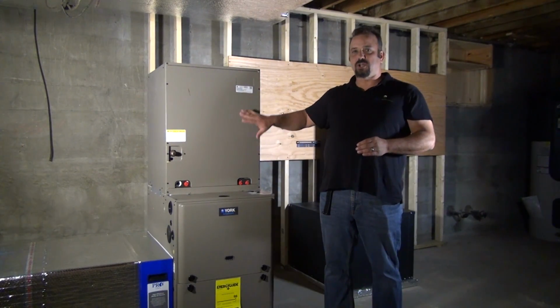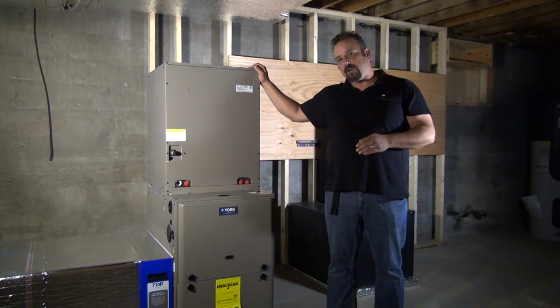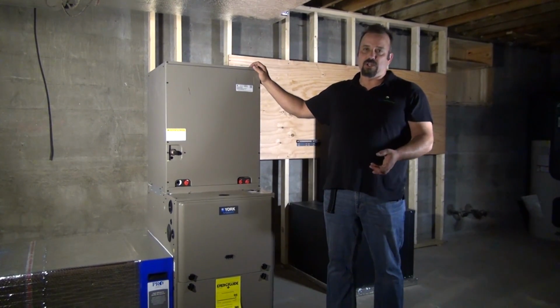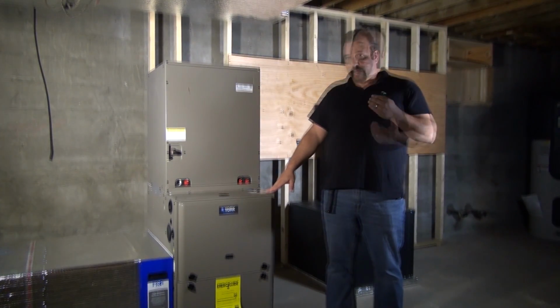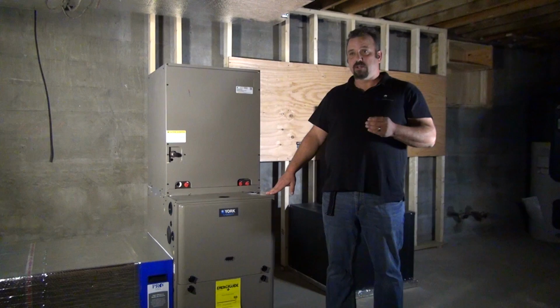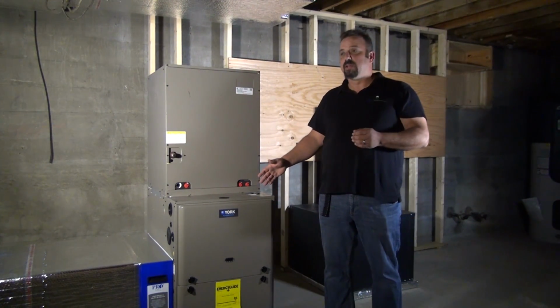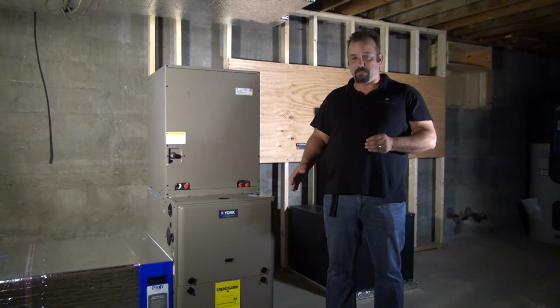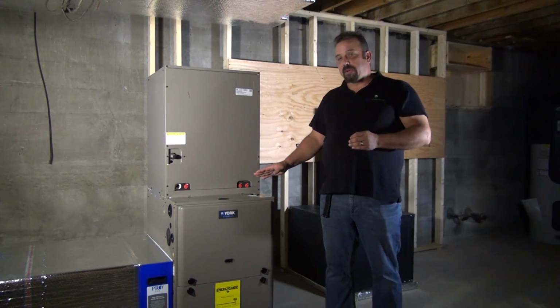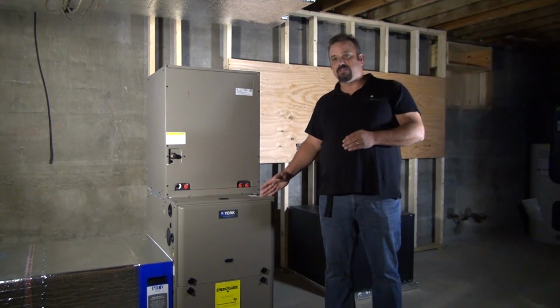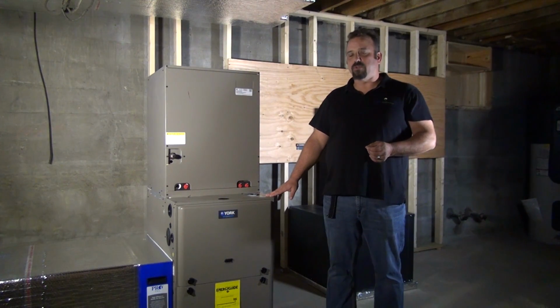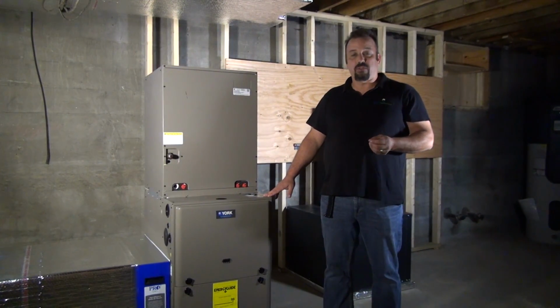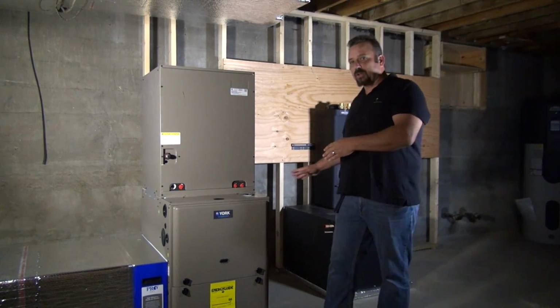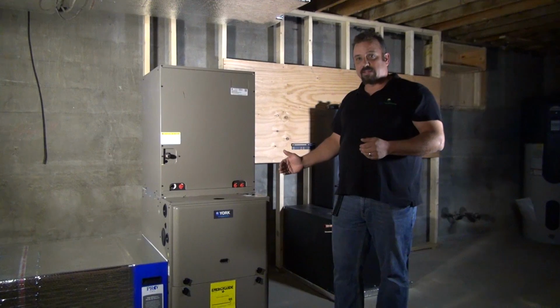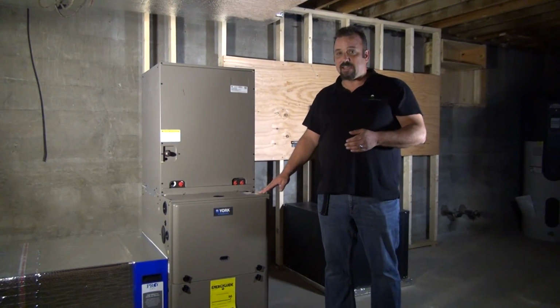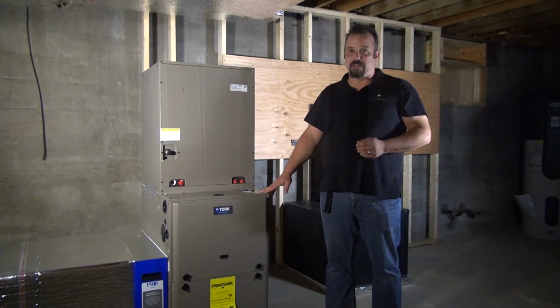Efficiencies are the same. As long as you match your geothermal heat pump with the proper evaporator section, you achieve the same efficiencies when you're running your geothermal, and you get the benefit of having the backup gas. The generator company who had originally sized this house for a generator to run the house, including a standard geothermal, said that the generator was going to need to be between a 22 and 24 kW generator at a cost of about $10,000. But by doing this instead of the straight geothermal and having this as the backup run off the generator, they were able to reduce it to a 12 kW generator at a cost of about $3,000 to $4,000. So this is about a $1,000 upgrade versus a packaged unit when you're going to install something like this. However, that's a significant savings versus the upgrade cost of spending that additional money on the generator.